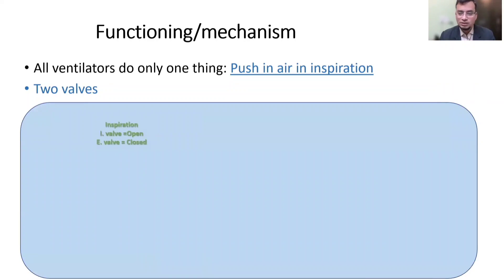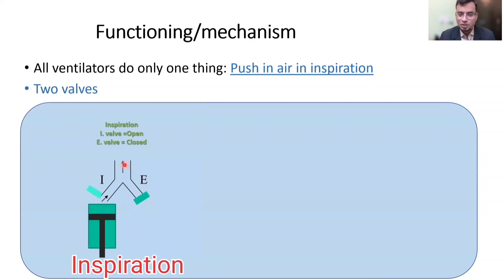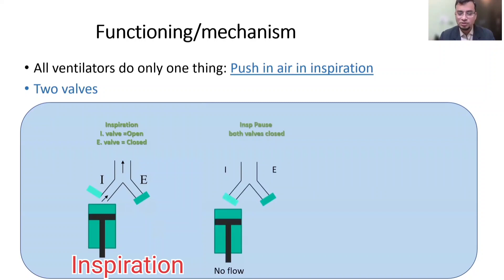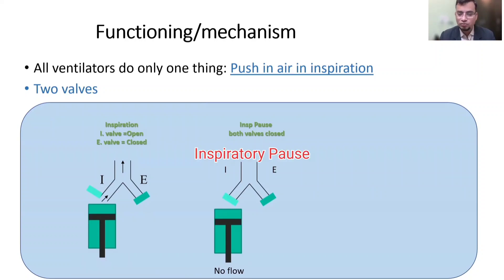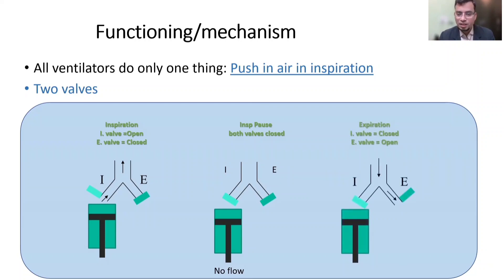Once inspiratory flow is generated, it needs to be controlled using two types of valves: inspiratory valves and expiratory valves. During inspiration, the expiratory valve closes and the inspiratory valve opens, delivering flow to the patient. After flow reaches the maximum value, the inspiratory valve closes once the set limit is reached. Then there is a situation called inspiratory pause where both valves are closed, usually kept between 5 to 15% of total inspiratory time. After the inspiratory pause, the expiratory valve opens, expiration starts, and expiratory flow goes to the maximum value, then slowly decreases over time until expiration ends.